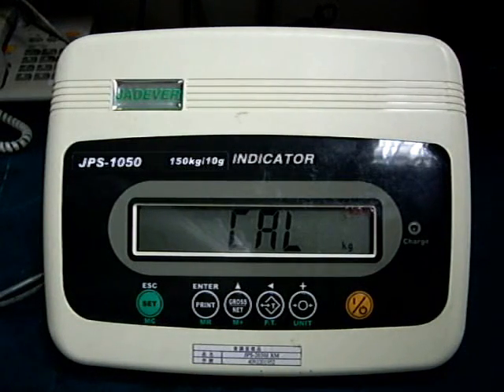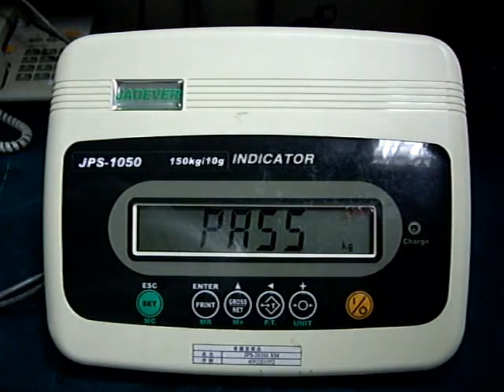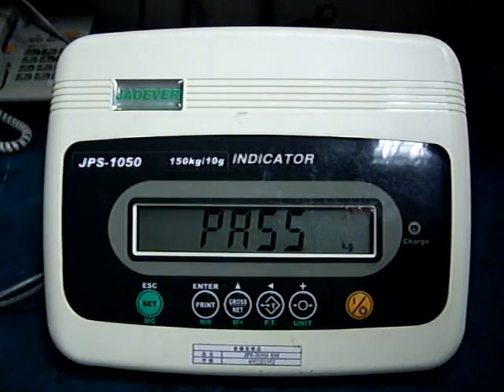The display will show CAL. The display will show PASS after the beep sounds. The span calibration has now been completed.